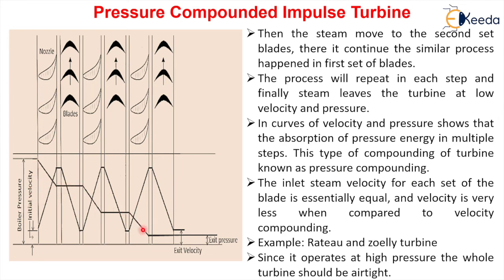The inlet steam velocity for each set of blades is essentially equal and much less compared to velocity compounding — in velocity compounding, velocity was reducing at each stage, but here velocity is approximately the same at the inlet of every moving blade. Examples of pressure compounded impulse turbines are the Rateau and Zoelly turbines. Since this turbine operates at high pressure, the whole turbine should be airtight to prevent steam leakage.